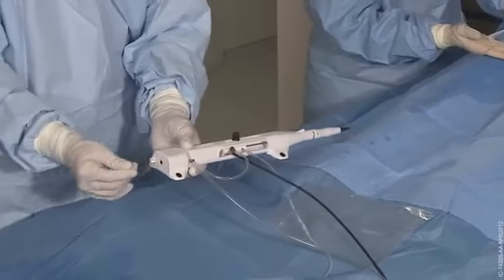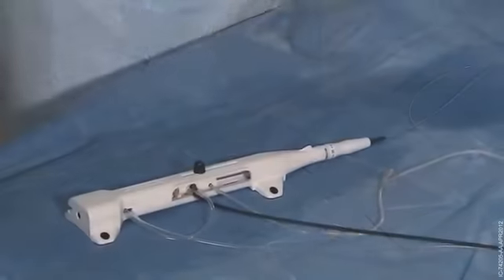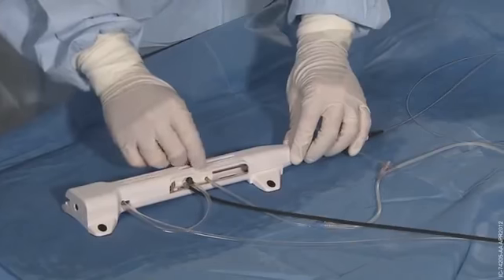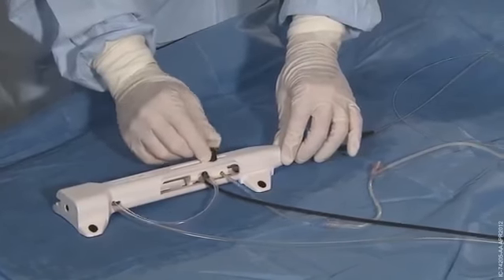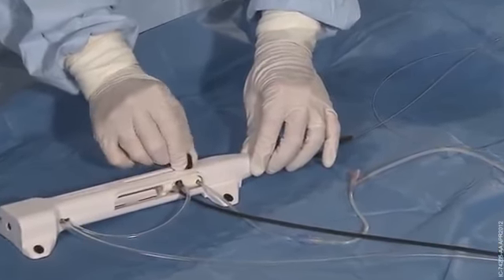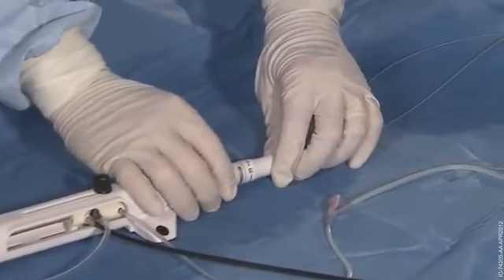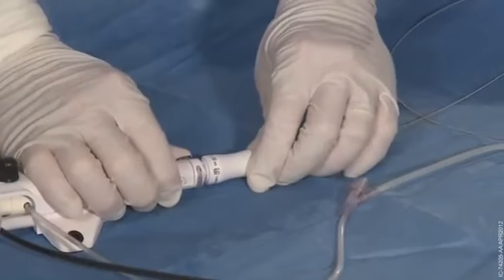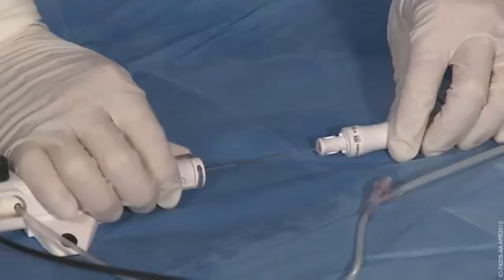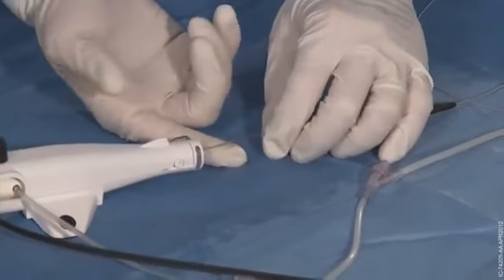During the procedure, you may wish to exchange burrs. To detach the catheter from the advancer, loosen the burr advancer knob and slide it forward, locking it into place. Using one hand, depress the catheter connection latch and separate the catheter from the advancer, exposing the drive shaft connection.